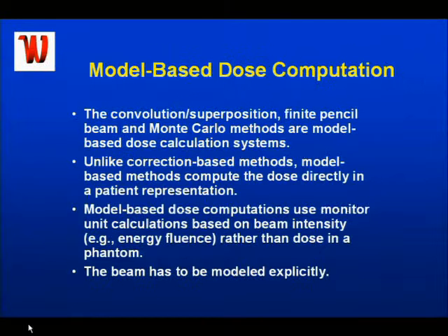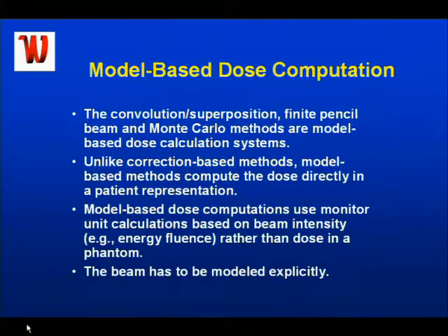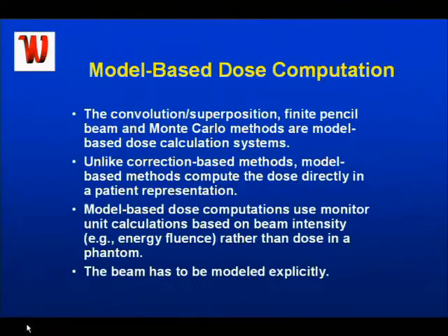The heterogeneity corrections they produced weren't that accurate, especially if you had both contour corrections, field modifiers, and serious heterogeneity issues. So really from the 90s, we started having what are called model-based dose calculations. Rather than starting from a measured dose distribution, you still need that measured water phantom data in order to characterize the models — you're creating models rather than using the actual dose distributions themselves.